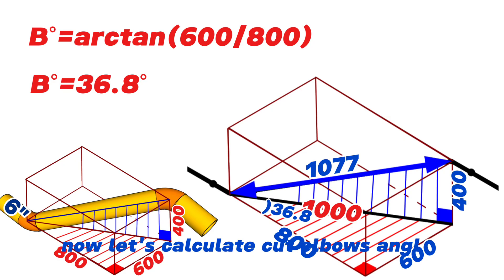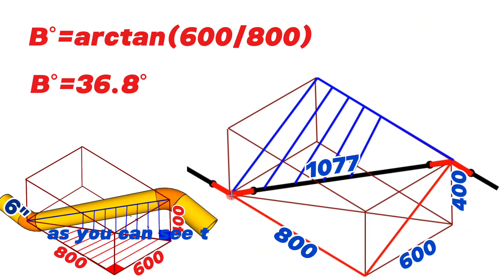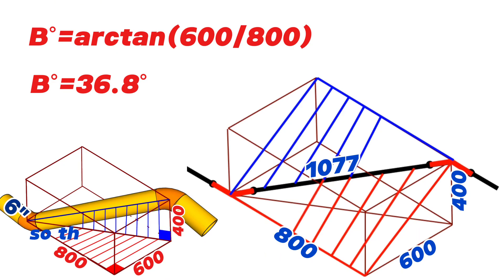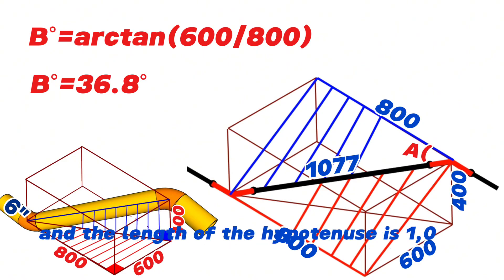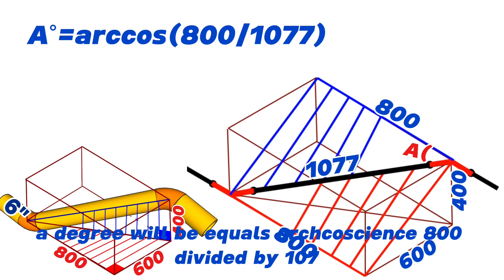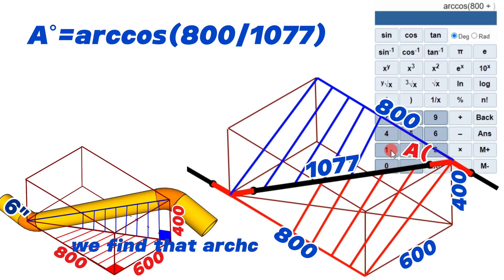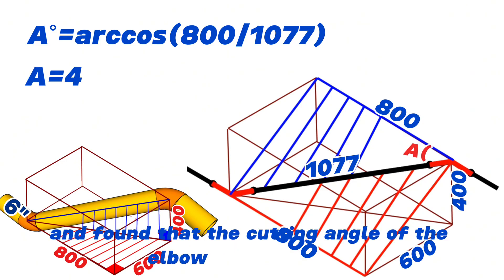Now let's calculate the cut elbow angles. We complete each elbow from the back to a right-angled triangle, provided that they are on the same plane. These right triangles formed by the dashed lines are equal to each other, so the intersection angle of the elbows will be the same. Let's mark these angles with letter A. In the right triangle, the adjacent side is 800mm and the hypotenuse is 1077mm. Therefore angle A equals arccosine of 800 divided by 1077, which equals 42 degrees.